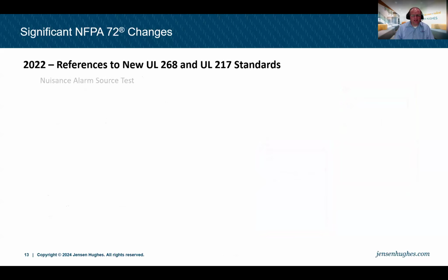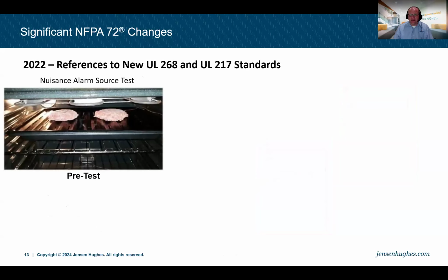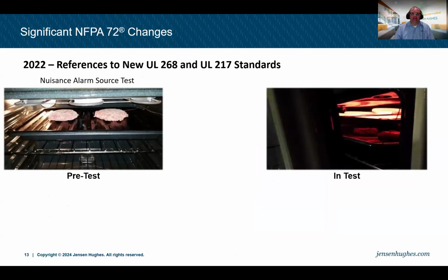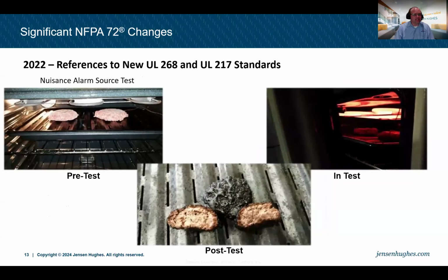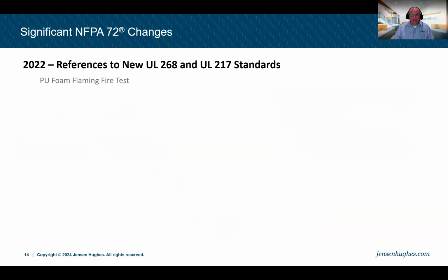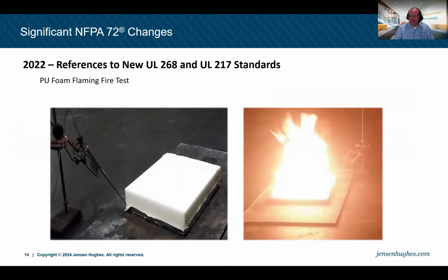So three tests were added, and you kind of get a picture of these. That nuisance alarm test is now known as the hamburger test. They take frozen hamburger, they broil it inside the test chamber. It comes out as these little briquettes, and basically they have to be able to survive and not alarm to the nuisance alarm created by a burning hamburger, as an example. But they do have to alarm when exposed to polyurethane foam. In this case, the flaming test. These are some pictures of what that flaming test looks like, taking foam and literally lighting it on fire and making sure our smoke alarms and smoke detectors are activating under that kind of alarm material.